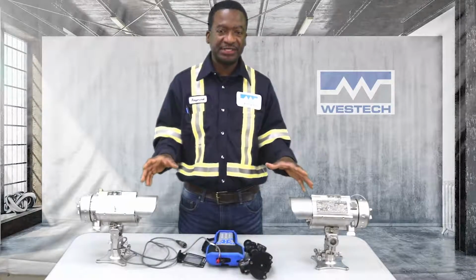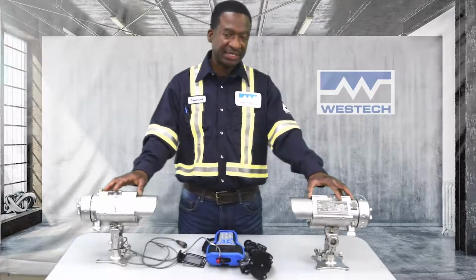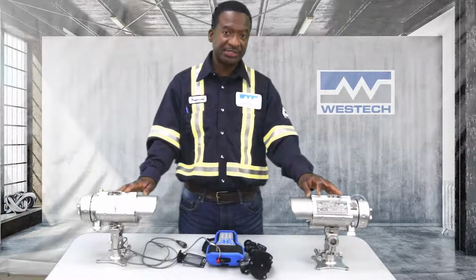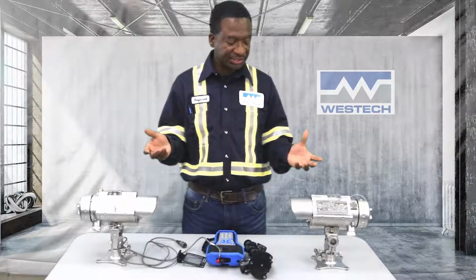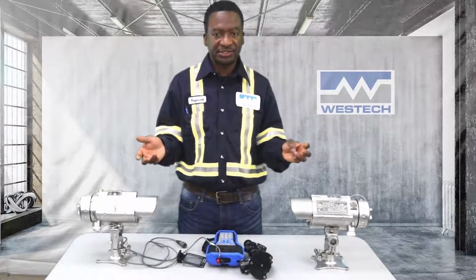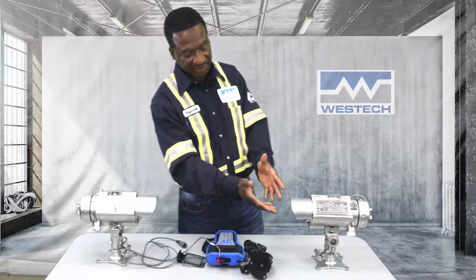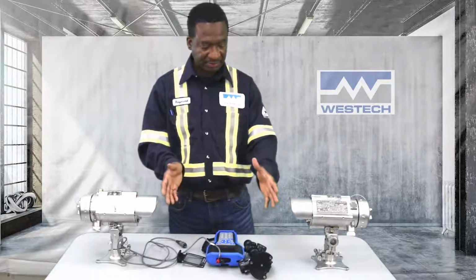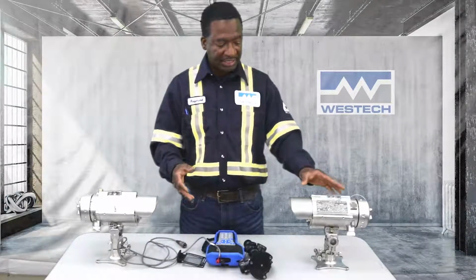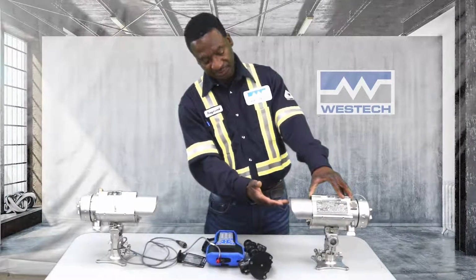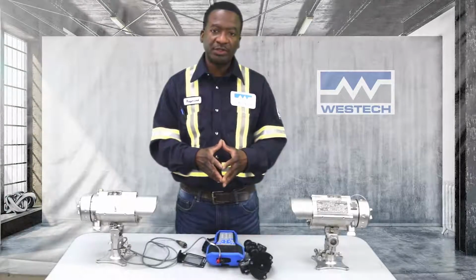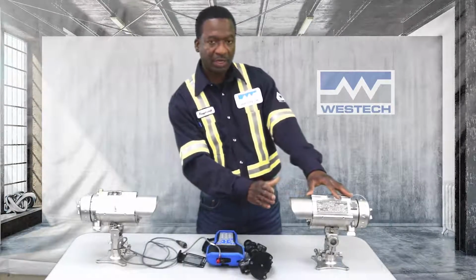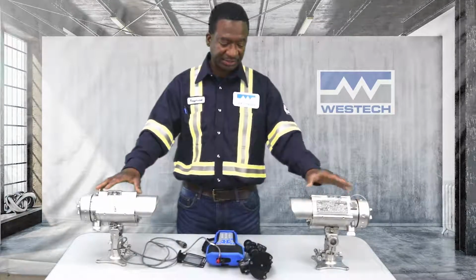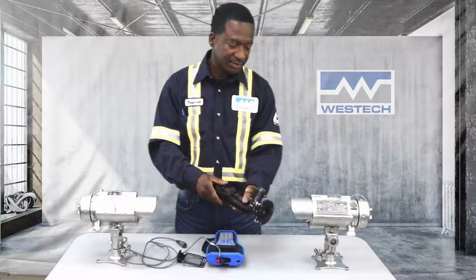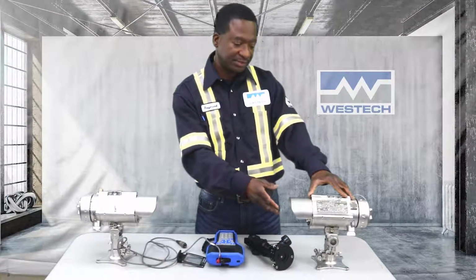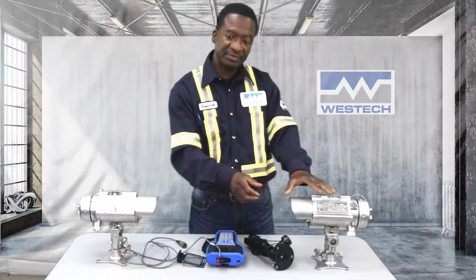One of the frequently asked questions is, what is involved in the maintenance of the detection system? The answer is not very much. The detection system should be checked around every 6 to 12 months. This involves a visual inspection of the lens, looking to make sure that nothing is in the line of sight of the detection system, and cleaning off the lens if required. If there is contaminant buildup or dust, clean it off with water, or if you have isopropyl alcohol and a clean towel, just wipe it off. After this is done, it becomes necessary to confirm the alignment, as in cleaning the face of the lens, the alignment of the detector itself may have shifted.